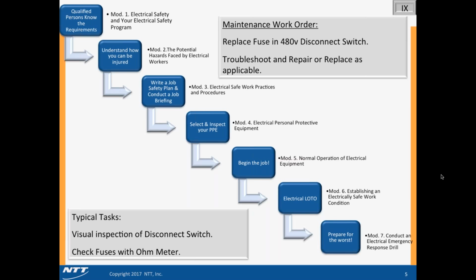The great debate in the electrical safety business has always been: will the covers on a piece of equipment, if they're all closed up and bolts are in place, protect me? NFPA 70E prior to the 2015 edition would always tell you not necessarily, you could not count on the covers to protect you completely. And the 2015 70E came out with a thing called normal operation of electrical equipment.